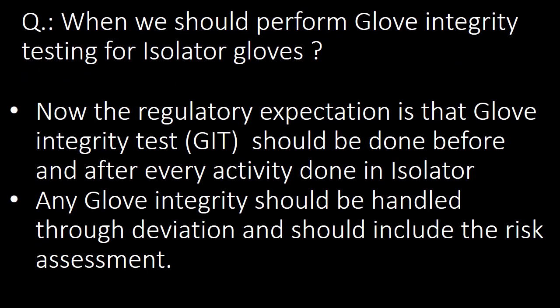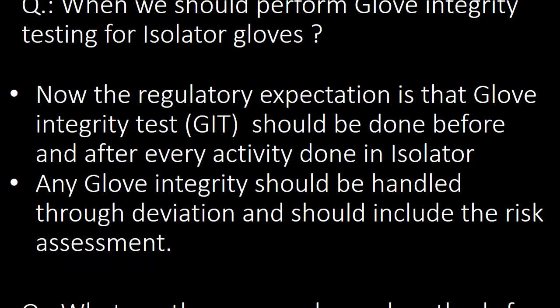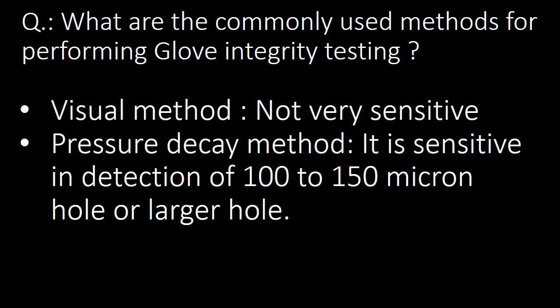The next question: when should we perform glove integrity testing for isolator gloves? The regulatory expectation is that glove integrity testing (GIT) should be done before and after every activity in the isolator. Any glove integrity failure should be handled through deviation and should include a risk assessment.